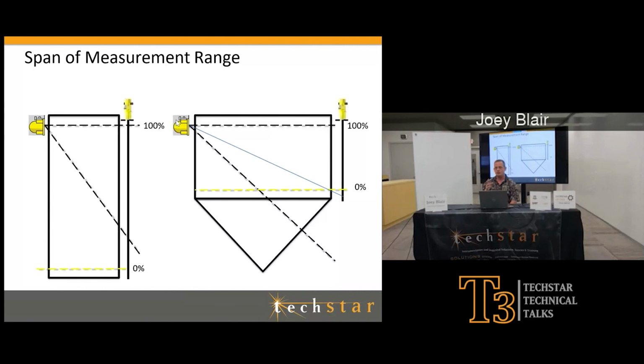In our second picture, you'll see my 100% looks good, right? You can see the dotted line goes across. It's going to reach just fine. But then my 45-degree, where my 0 is above, and I've got radiation coming below it. That's perfectly fine, okay? I don't have an issue with that. That'll work. The only thing that we might want to look at on this one, if I was doing this commissioning, is that field below the detector where that radiation beam is still shining. I would use my Geiger counter in that area.